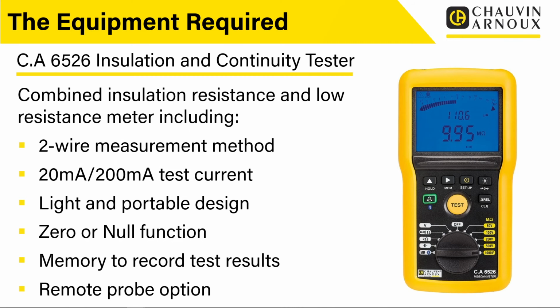These are great little products. As we discussed, they're a simple 2-wire measurement, but they do a really good job, and they're a really useful addition to most electricians' toolboxes. It's a combined insulation and continuity tester, so you can do insulation resistance measurements and your 2-wire resistance measurements. This would be suitable for measuring under the 18th edition BS 7671 down to those sort of levels, 0.01 of an ohm type readings. Really great, portable, rugged, reliable, and very easy to use.